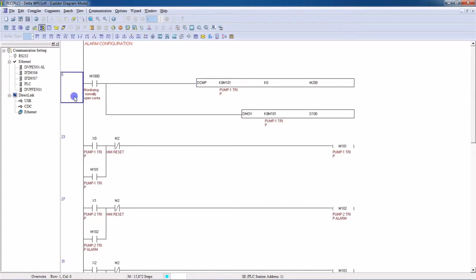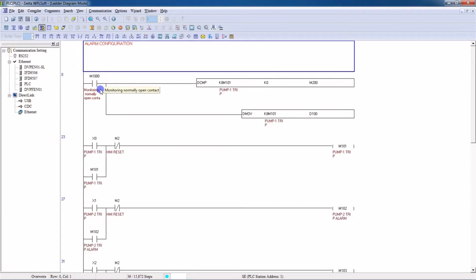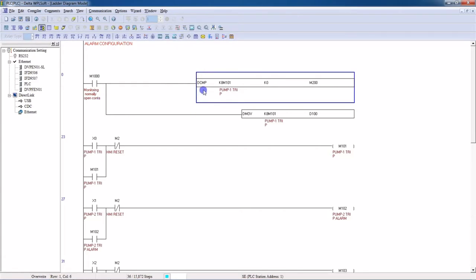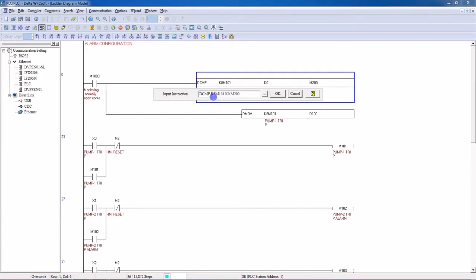First we have to write down the DCMP instruction — this is a comparison instruction, but we use this instruction for alarms. This is the standard format for alarm. You have to put K8M here without any space, then take an M register — I have taken M101, so my alarms will start from M101 — then K0, then M200. Click OK.